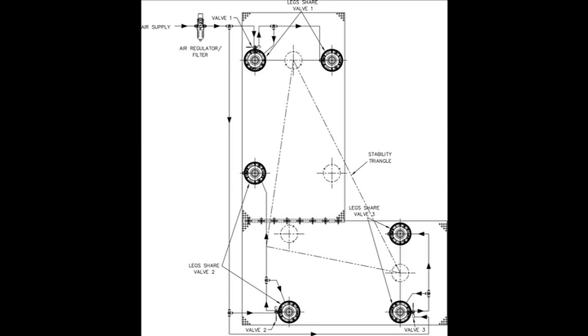In this next example, an L-shaped doubler system is shown being supported by six S2000 isolators, three for each section. Again, the output of the ARF feeds three leveling valves for the system, but because there are six legs in total, each valve is used to control two legs.